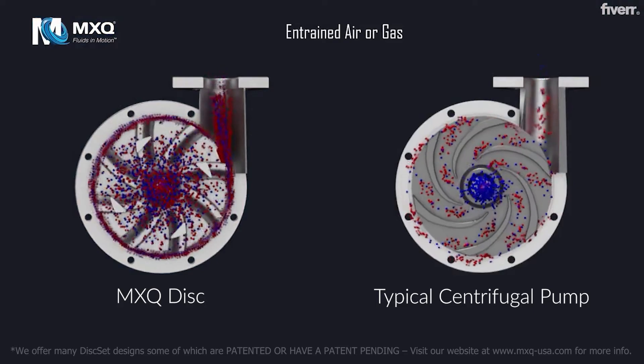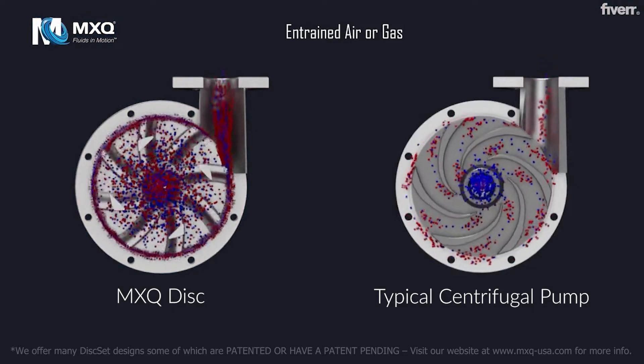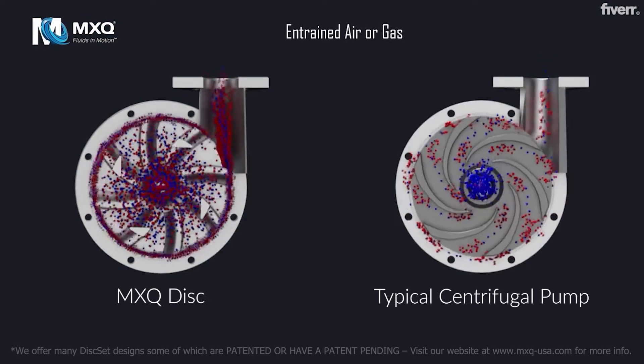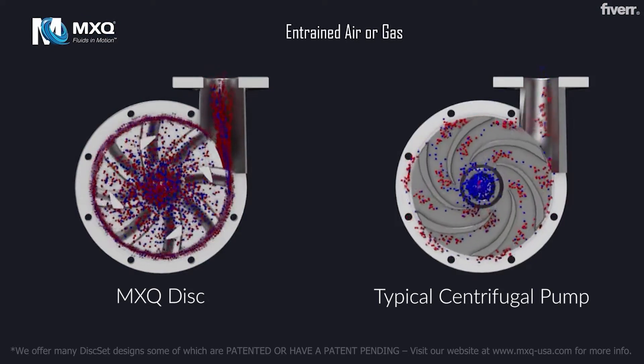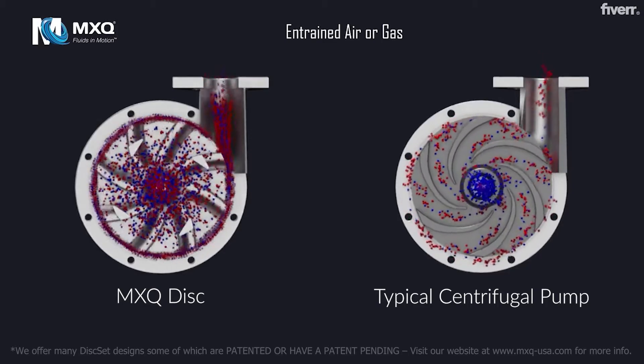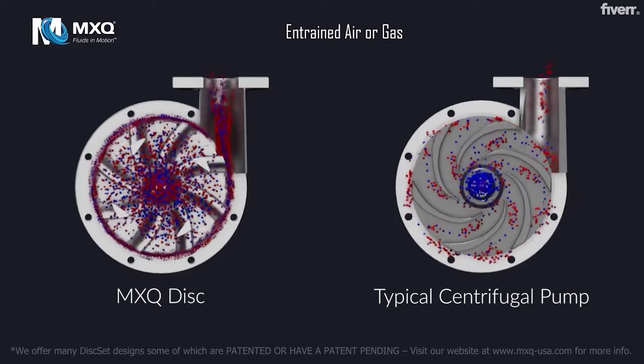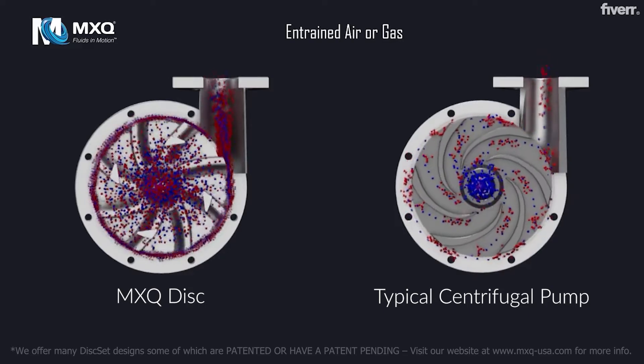Entrained Air and Gas. In a typical centrifugal pump, the centrifugal force generated by the rotation of the vanes sends higher density fluid to the periphery and constrains air and gas at the eye of the impeller. This causes uneven loading resulting in inefficiency and failure.